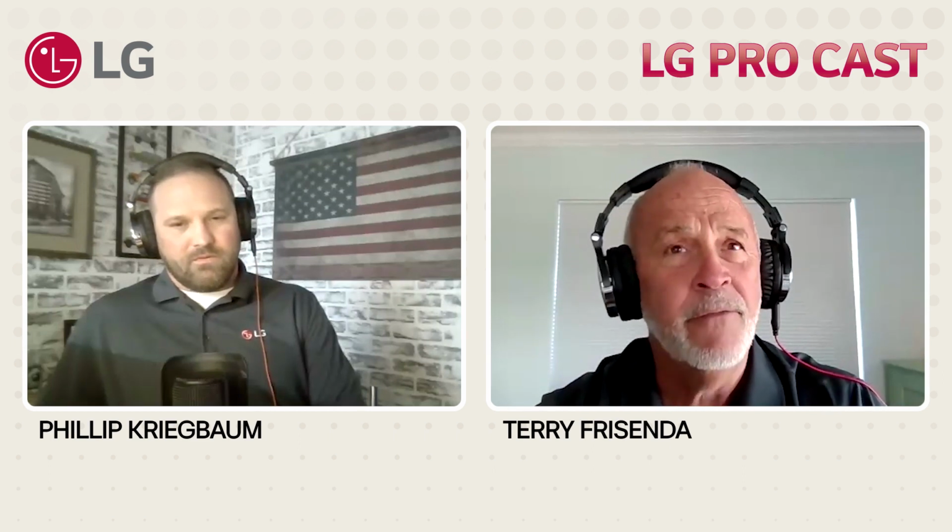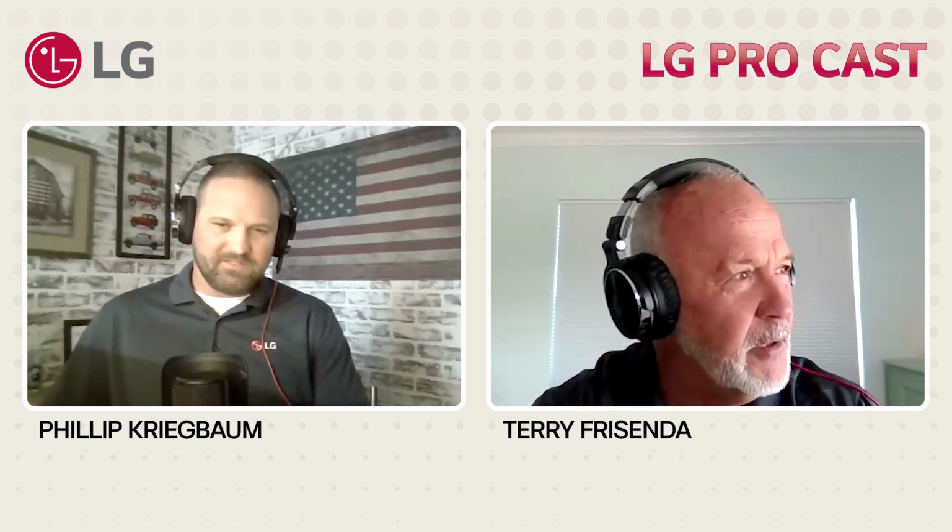But, back to VRF, when you look at how that system operates, and I spent some time today before this podcast just grounding myself and looking at some animated detail and all this crazy nerd stuff to be able to talk about heat pump and cold climate and inverter driven. One of the things that came out of that little session was that by changing the speed of the compressor, the physics allow the refrigerant to boil at different temperatures and shed heat and absorb heat and be able to go outside and get the heat that is available and bring it inside. And that's pretty cool. And why inverter and why variable refrigerant flow? Because I'm only consuming the power necessary to make the exact amount of BTUs. And that's what hasn't happened in traditional heat pumps, as folks know it.